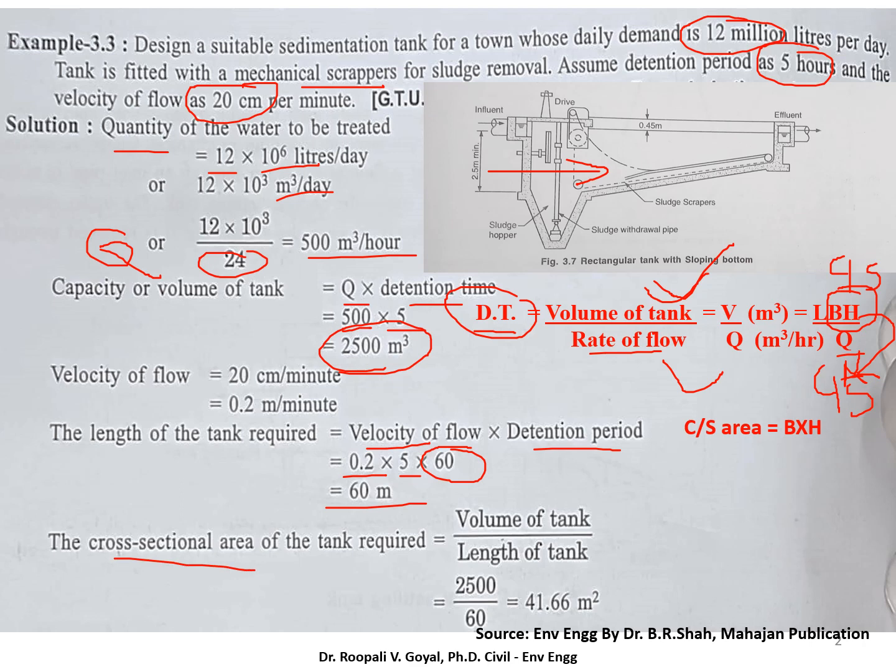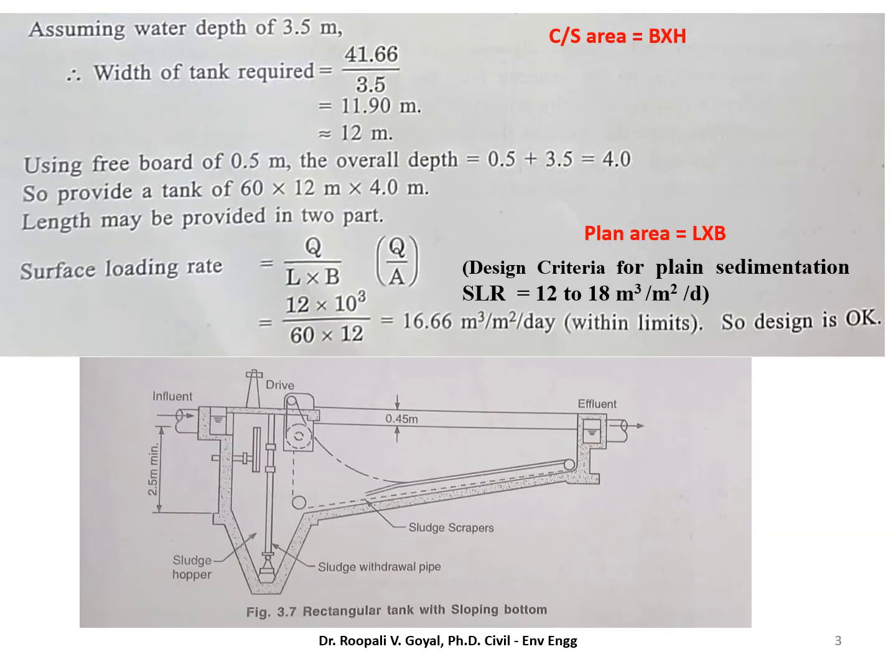Now we have to find out the cross sectional area. So this cross sectional area, as I told you, it is volume of tank divided by length of tank. If it is LBH, this is a cross sectional area. So here you can see volume is equal to LBH. If we find out the volume divided by L, so here you can get this cross sectional area, 2500 volume, 60 is length. So you will get 41.66 meters square as cross sectional area. And the cross sectional area is B into H.